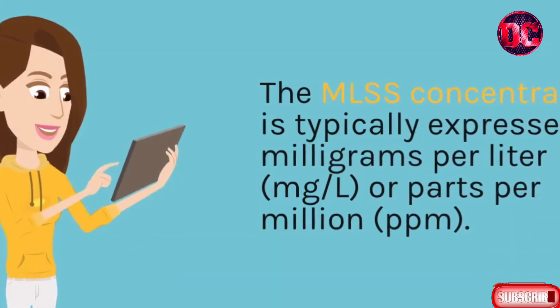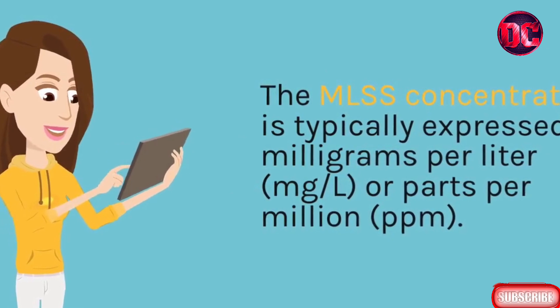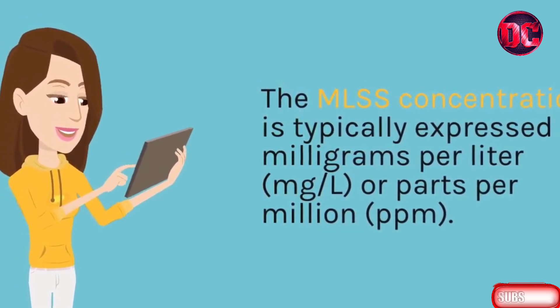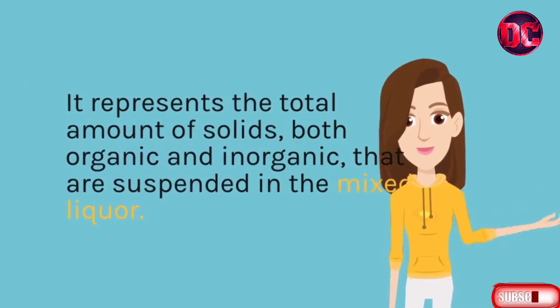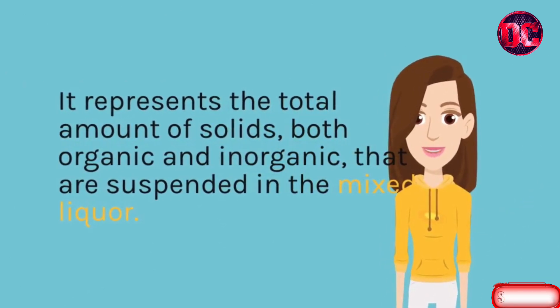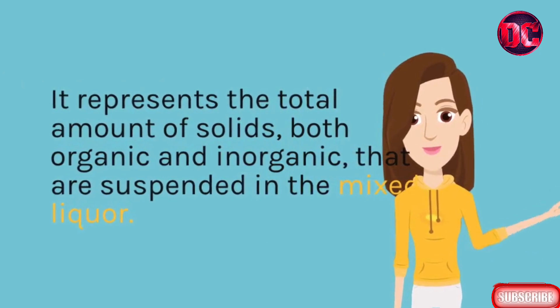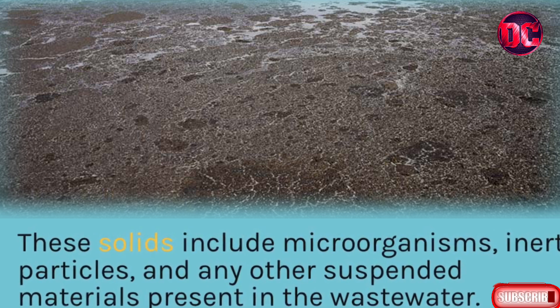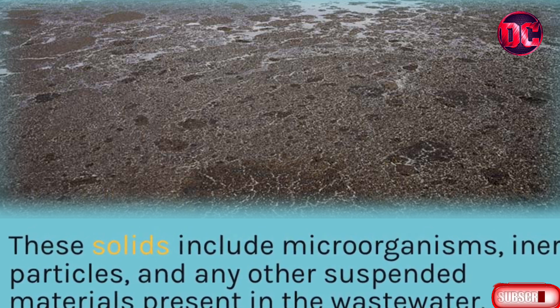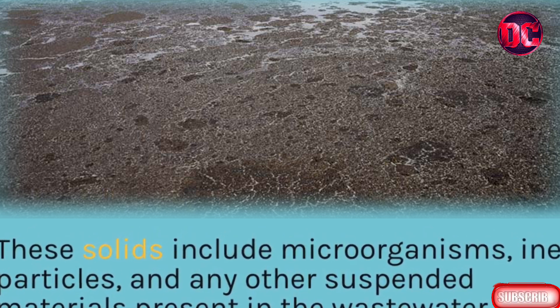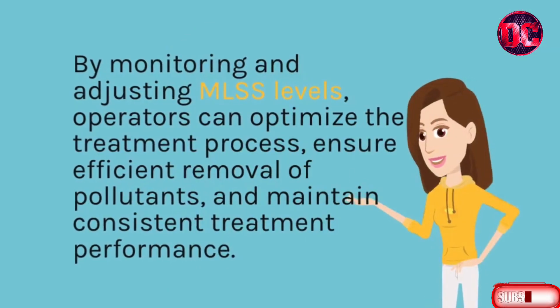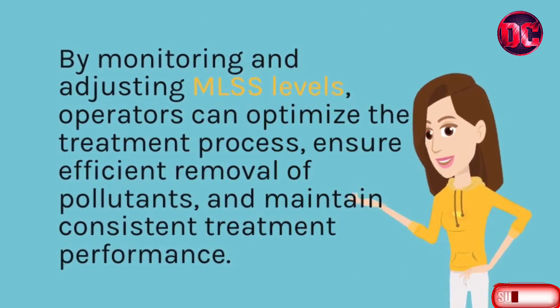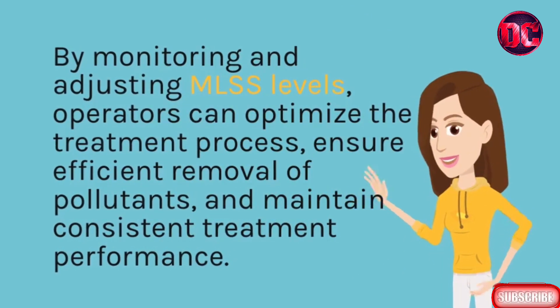The MLSS concentration is typically expressed in milligrams per liter (mg/L) or parts per million (ppm). It represents the total amount of solids — both organic and inorganic — that are suspended in the mixed liquor. These solids include microorganisms, inert particles, and any other suspended materials present in the wastewater. By monitoring and adjusting MLSS levels, operators can optimize the treatment process, ensure efficient removal of pollutants, and maintain consistent treatment performance.